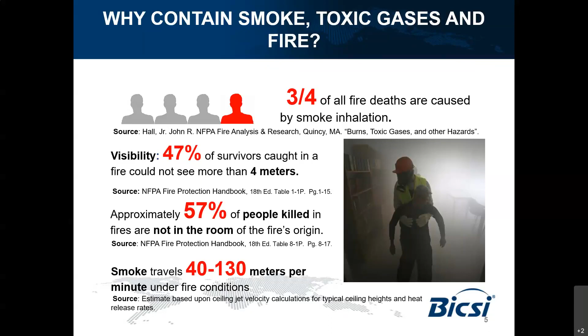So, a quick question: what is the leading killer in fire? I think I also indicated this in the previous slide. We all know that it is the smoke and the toxic gases. We are not only talking about the heat in case of fire, but also the smoke transfer. That's why, even if a small data cable goes through a wall, we need to properly seal that opening. And in addition, the biggest threat to damaging communication and server equipment within the building is also smoke and products of combustion.